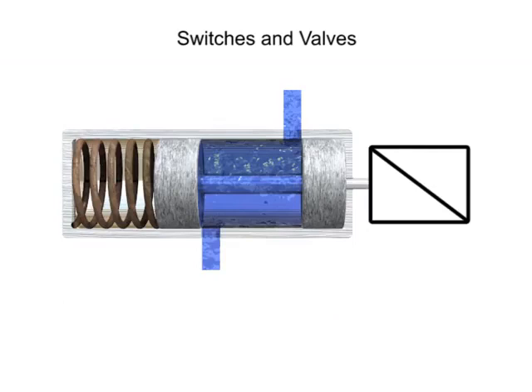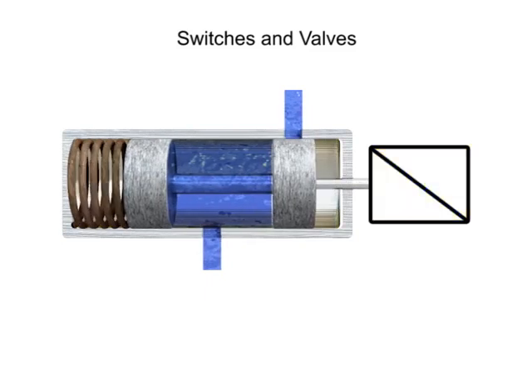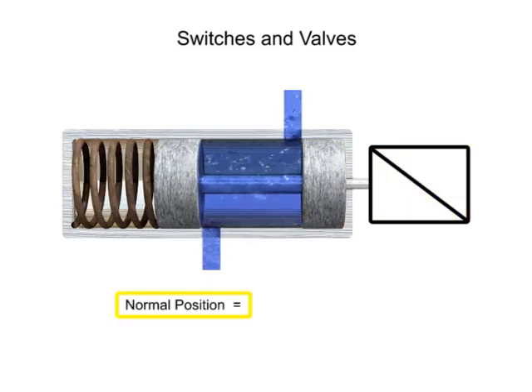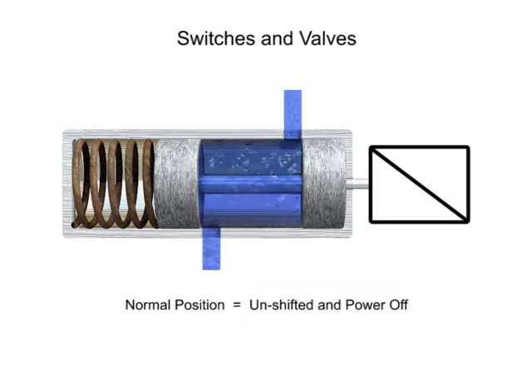Fluid valves are typically described as being either in the open or closed position. The open position allows the flow of fluid while the closed position prevents flow. The normal position of the valve is defined as the position of the valve when its spool is unshifted and the power is off. This means that any mechanical actuators, such as springs, are in their non-actuated positions.